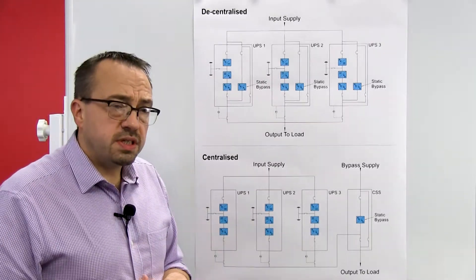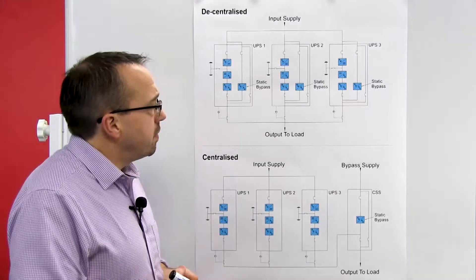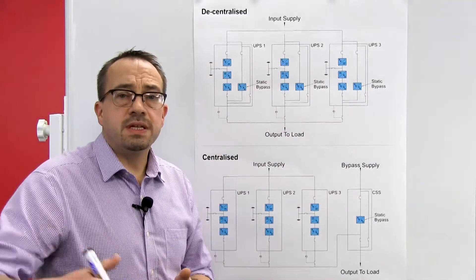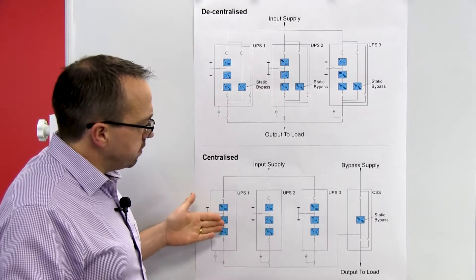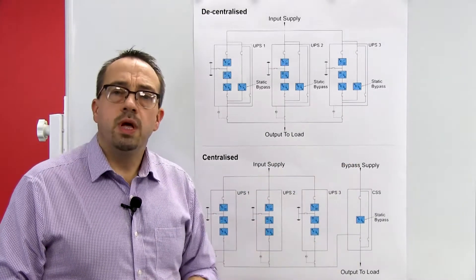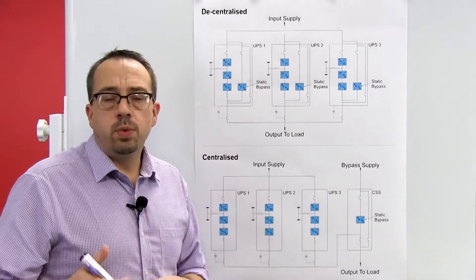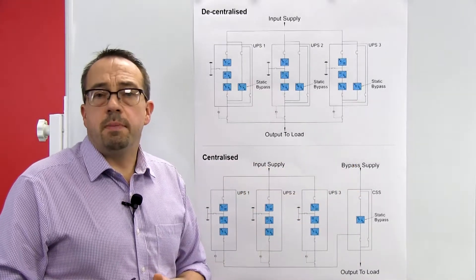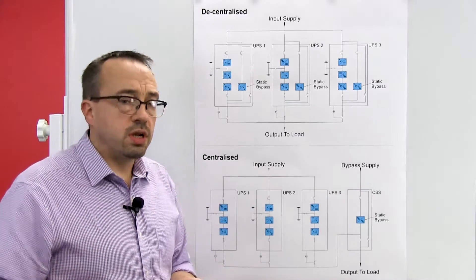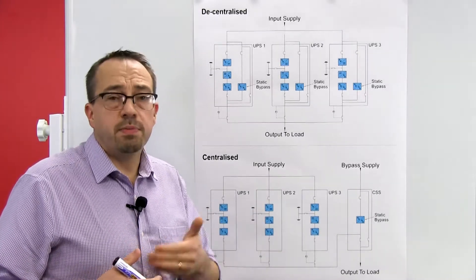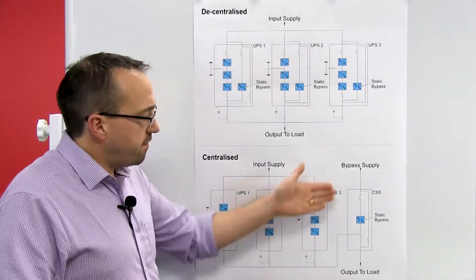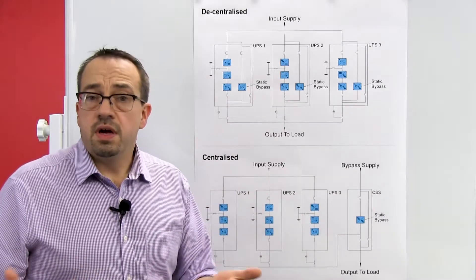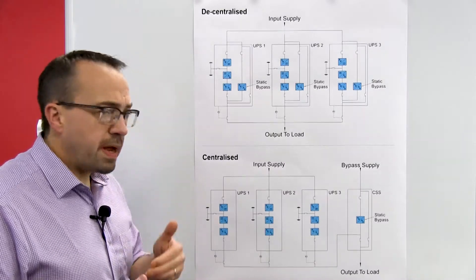You also have to consider initial investment and future planning. With a decentralized system you can simply add modules in the future to increase overall capacity. With a centralized system you must consider the rating of the bypass module from day one — if it's not rated to handle future load growth, you may need to replace it with a larger module. Conversely, if you over-specify it from day one it could be a very expensive purchase, leaving you with a static bypass module far oversized for the final installation.